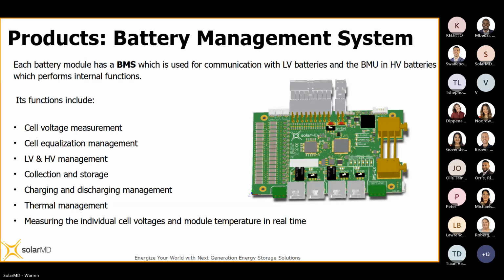Another role of the BMS in communicating with the inverter is reporting how fast the battery can be charged and discharged. Every battery has a limit, referred to as the C rating. The BMS tells the inverter, for example, you can discharge me at 100 amps, or charge me at 100 amps. So the BMS communicates this critical information to the inverter so it knows what it's working with.